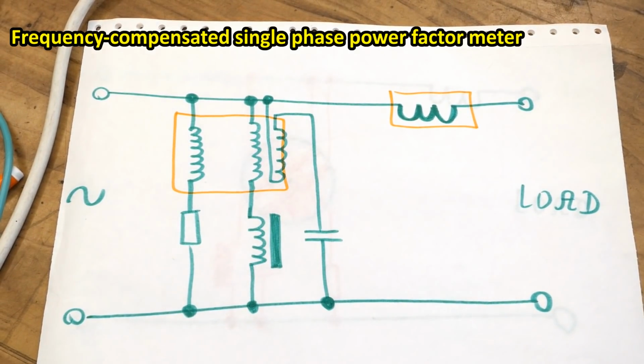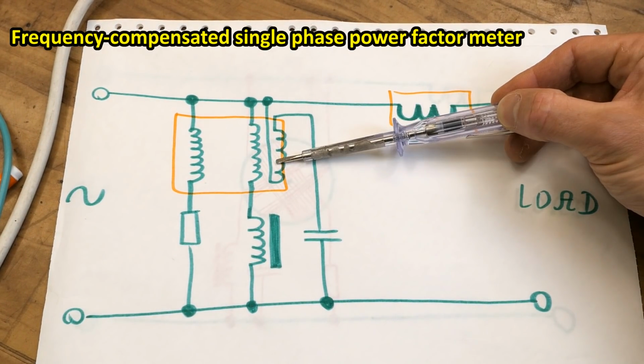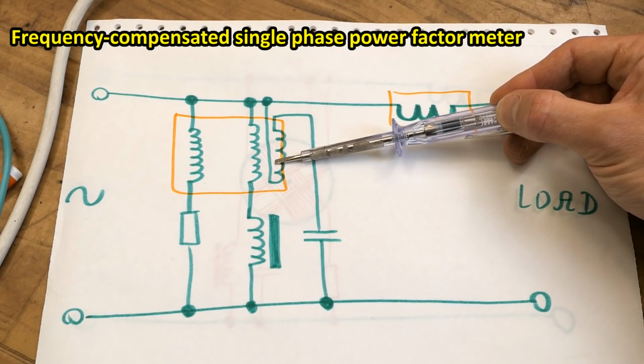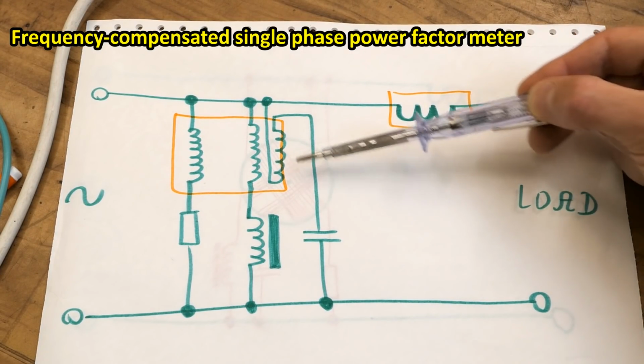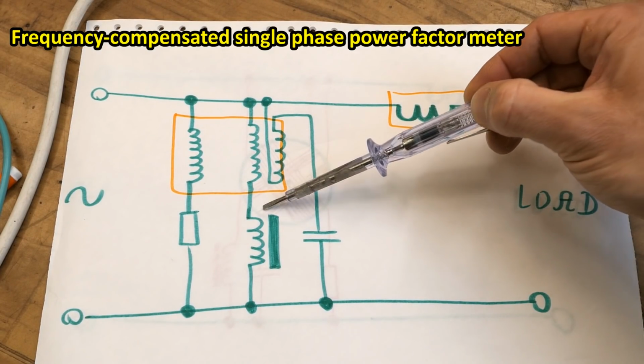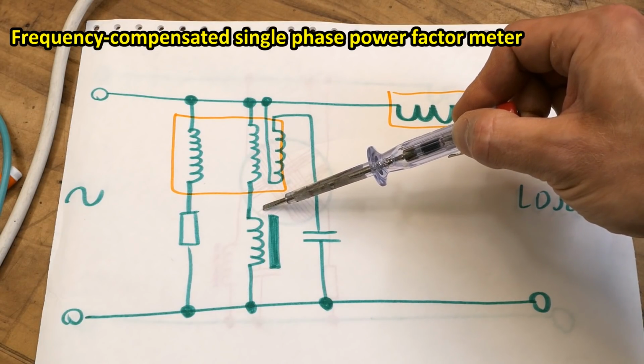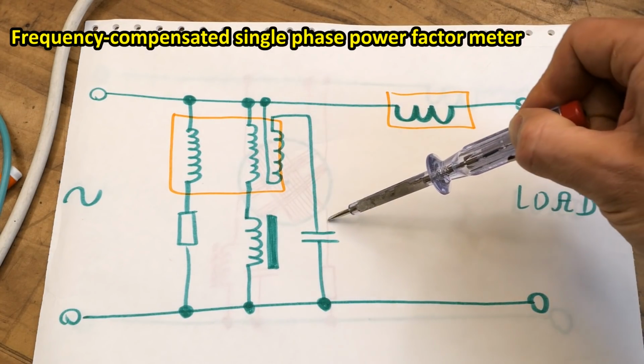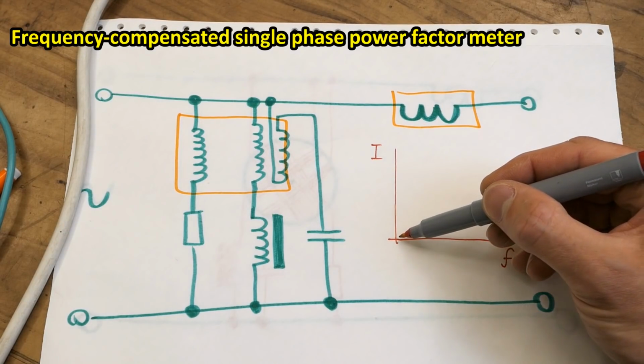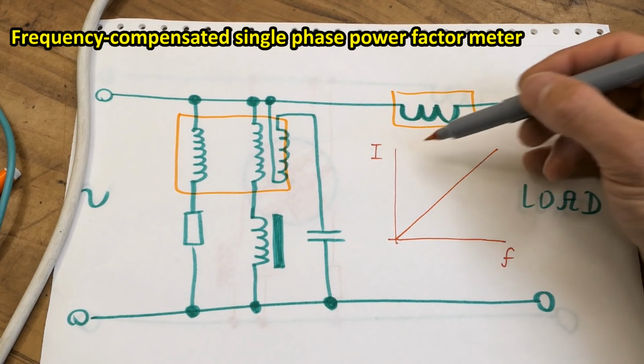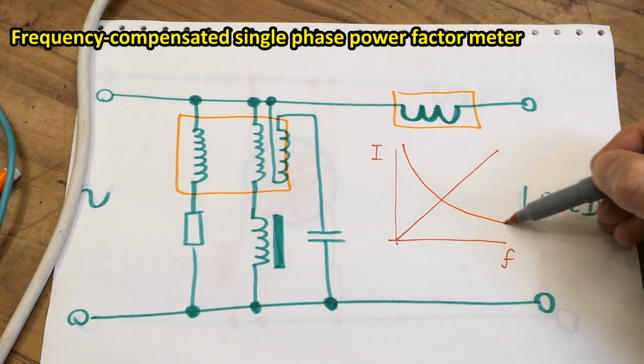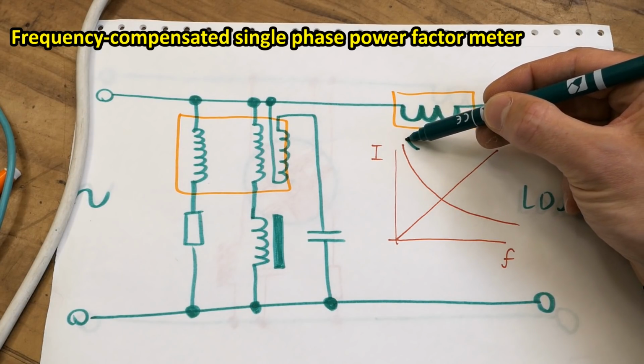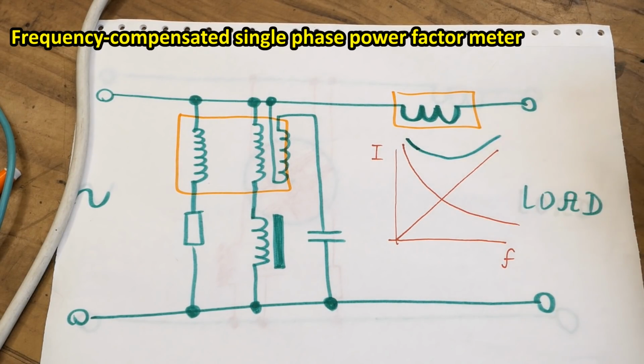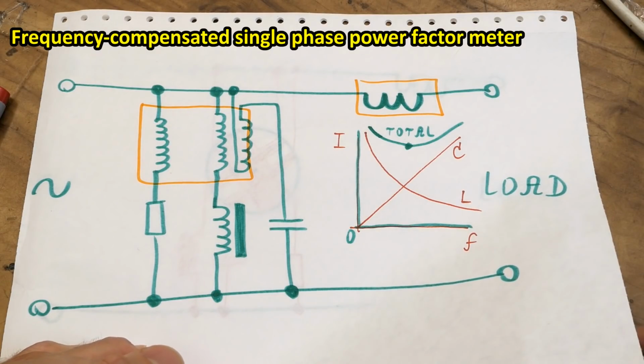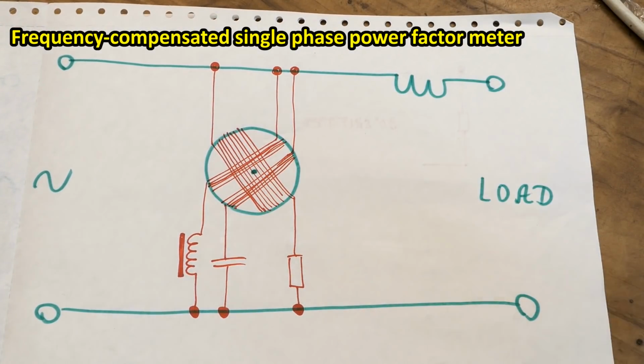And then of course the magnetic field of this pair of coils in total doesn't change so steeply with the frequency. Because at a higher frequency the capacitor passes more current and the inductor less current, and at a lower frequency the inductor passes more current and the capacitor less current. With just a capacitor the current goes up with the frequency, with just an inductor the current goes down with the frequency. But the total is nearly flat near the nominal frequency. You're operating it somewhere here. So that's a single phase power factor meter which is less skewed by the frequency variation.